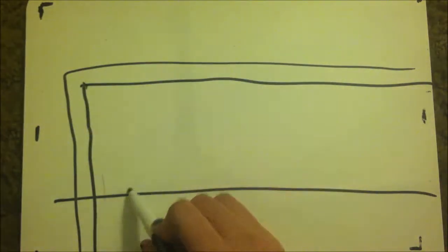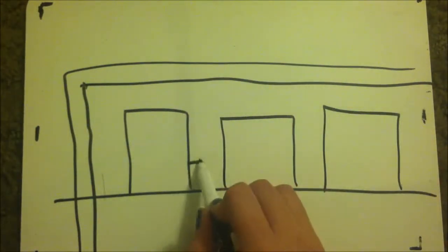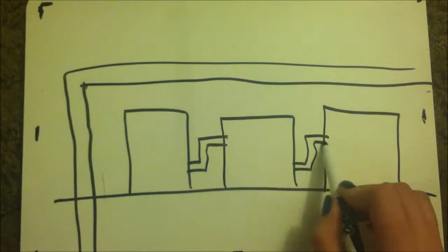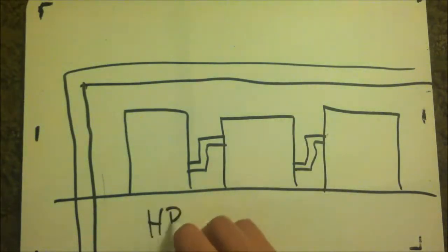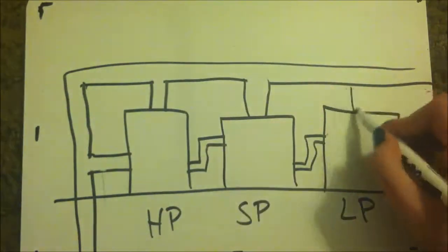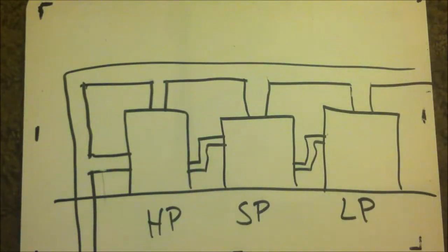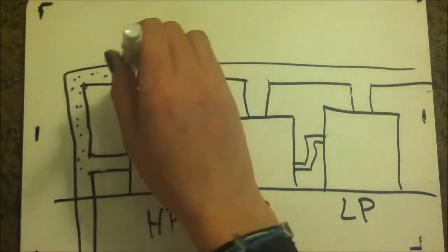As the liquid gets closer to the surface, the pressure is reduced. Because of this, a small amount of fluid in the well will turn or flash into steam. A combination of superheated fluid and steam flows from the pipelines to a wellhead separator. The pressure of the superheated fluid decreases in a high-pressure crystallizer, causing most of the superheated fluid to vaporize quickly and flash into high-pressure steam.